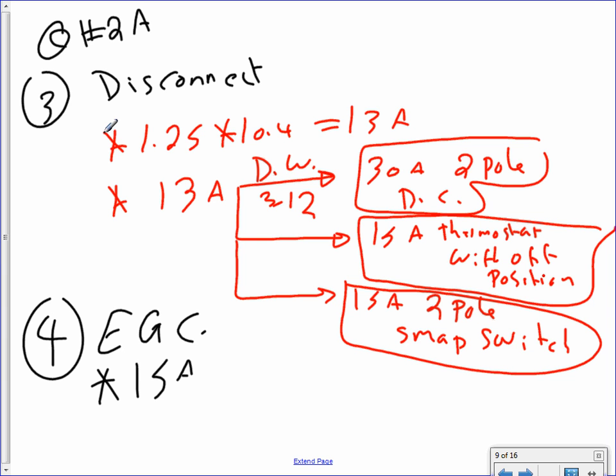Why? Because the amps are small, on smaller equipment and baseboard heaters. So let me tell you the most common option you're going to find. And I want you to highlight. The most common option will be the thermostat itself. Can you guys write? My thermostat that has an off position, inline thermostat will act as your disconnect. Right? When you put them in, your thermostat has an off position. That's your disconnect for the equipment. Can you guys highlight that one? The 15 amp? That's what we typically do with these. Any one of them will do as a disconnect though.